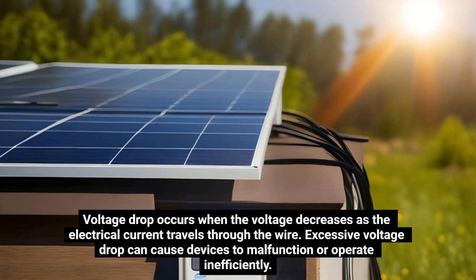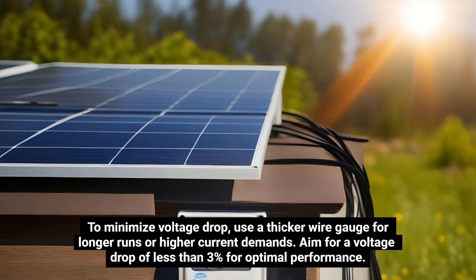Voltage drop and its impact. Voltage drop occurs when the voltage decreases as the electrical current travels through the wire. Excessive voltage drop can cause devices to malfunction or operate inefficiently. To minimize voltage drop, use a thicker wire gauge for longer runs or higher current demands. Aim for a voltage drop of less than 3% for optimal performance.